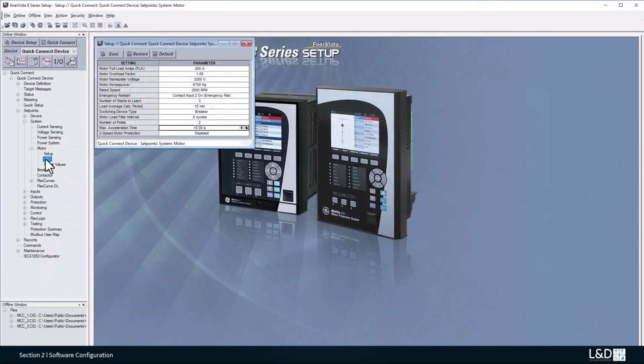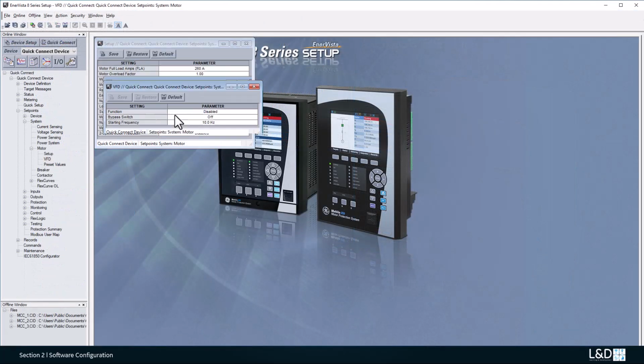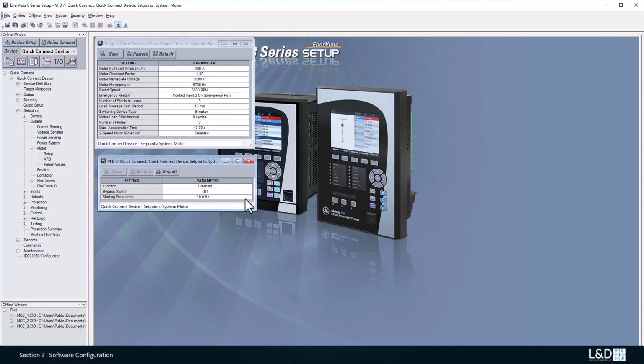The VFD (variable frequency drive) is under the motor setup. This function must be enabled in order to ensure the proper performance of the 859 relay for the motor application with VFD. There are 2 typical VFD motor applications. First is motor starts and running through the VFD. The second one is motor starts through the VFD but running through the bypass switch.